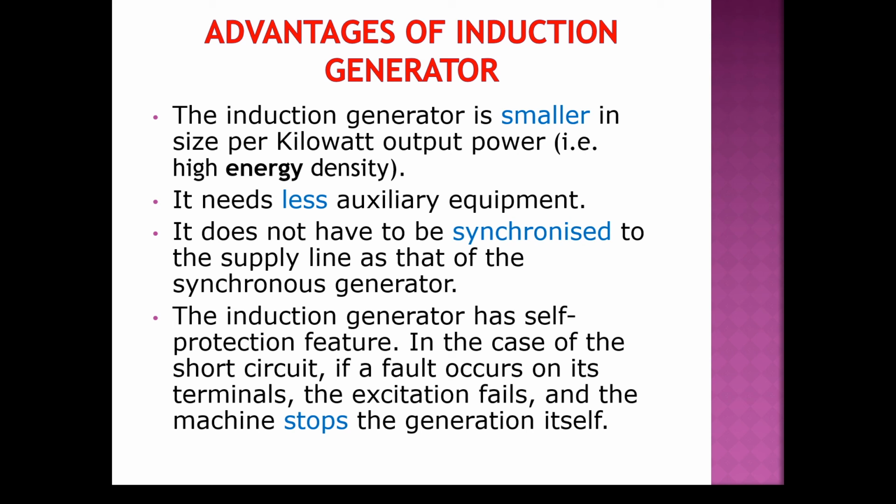Advantages of the induction generator continued. The induction generator will be smaller in size per kilowatt output power. It needs less auxiliary equipment. It does not have to be synchronized to the supply line as is the case with a synchronous generator. And the induction generator has a self-protection feature. That is, in case of any short circuit, if any fault occurs on the terminals or excitation fails, the machine will stop generating by itself.